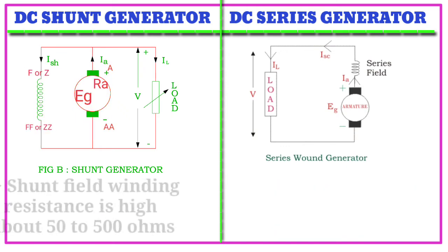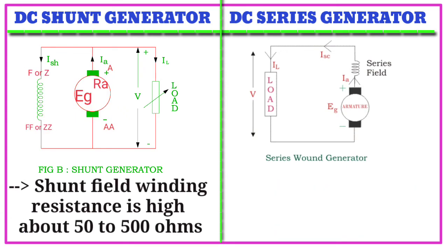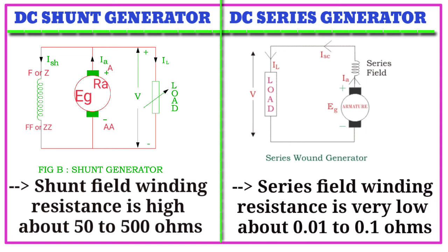Fourth point: shunt field winding resistance is high, about 50 to 500 ohms, whereas series field winding resistance is very low, about 0.01 to 0.1 ohms.